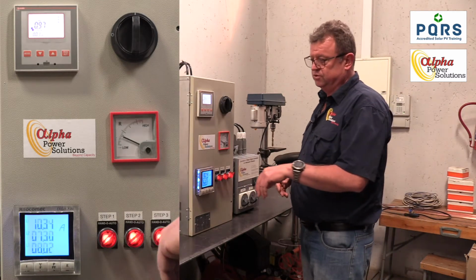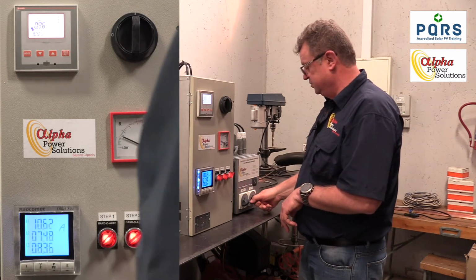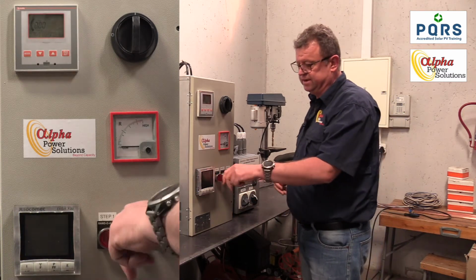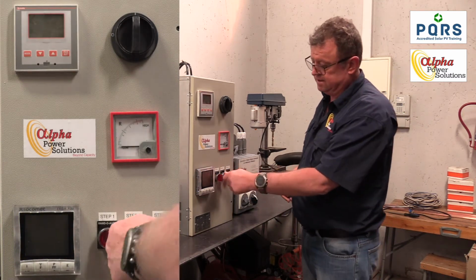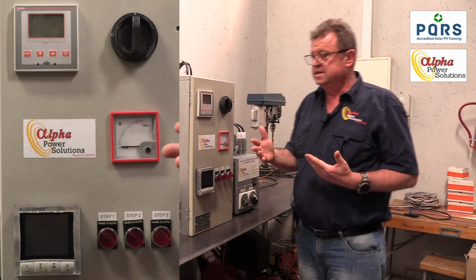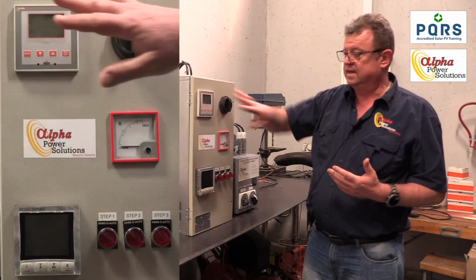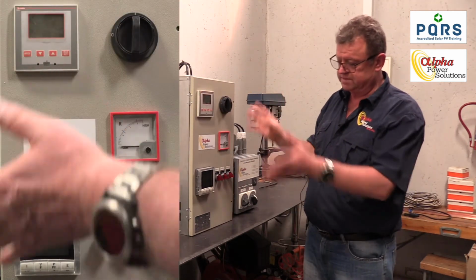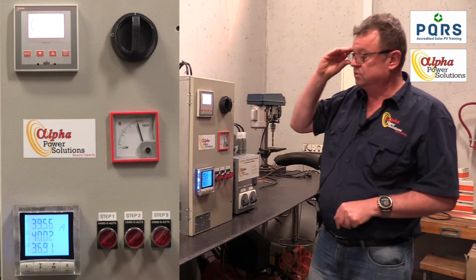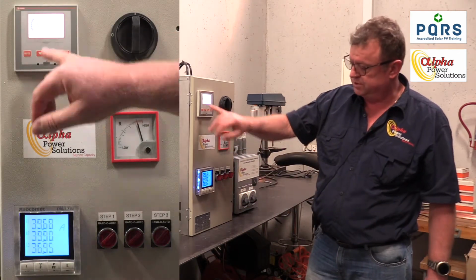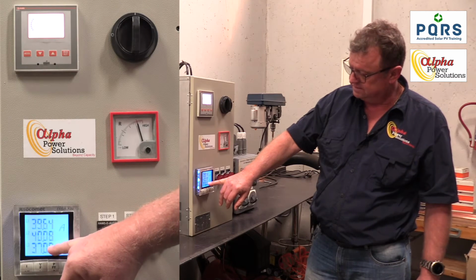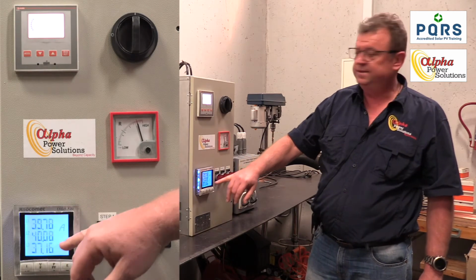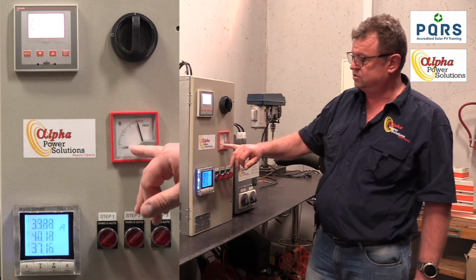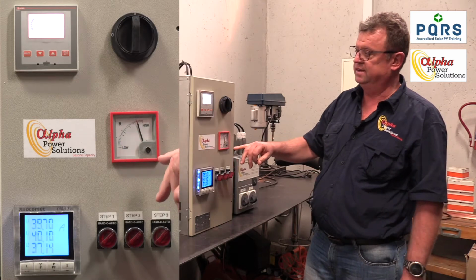I also want to show you what happens. This was now done in manual mode, and the controller here had no control over what was happening. So the power factor is still very poor. There's no banks in. The current is pretty high. And the costs for running the motor are pretty high.